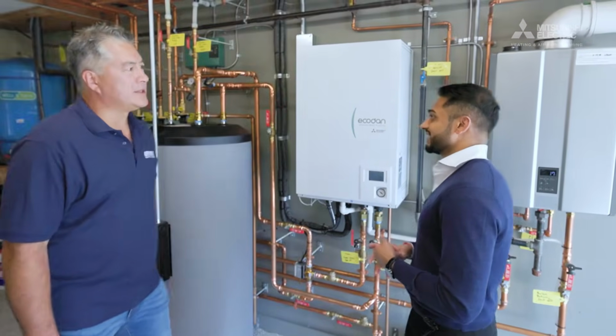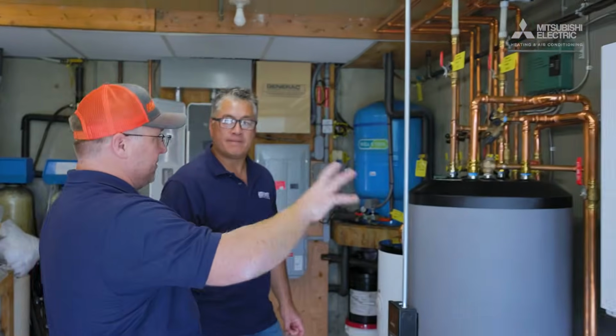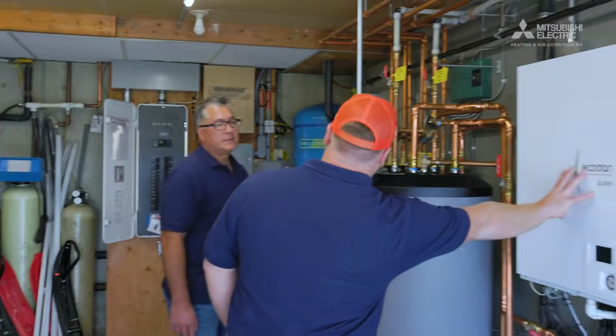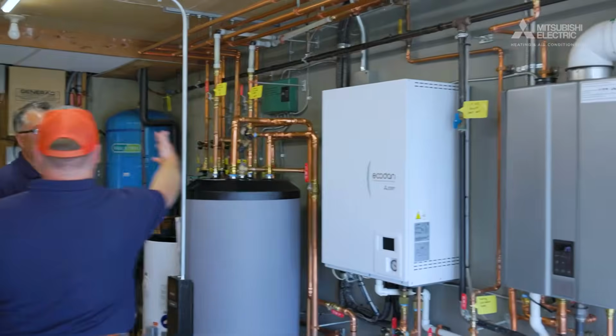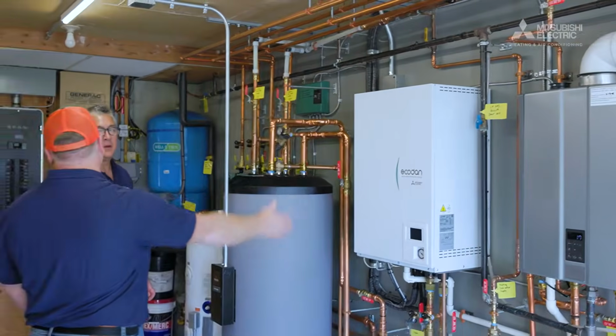The Ecodan system is unlike other heating equipment that we've installed in the past. Very straightforward, it can be installed in any plumbing piping application. It's a lighter weight product, being able to do a wall-hung piece of equipment that weighs half of the weight of a standard gas-fired boiler, not having to deal with cast iron boilers that are very, very heavy.